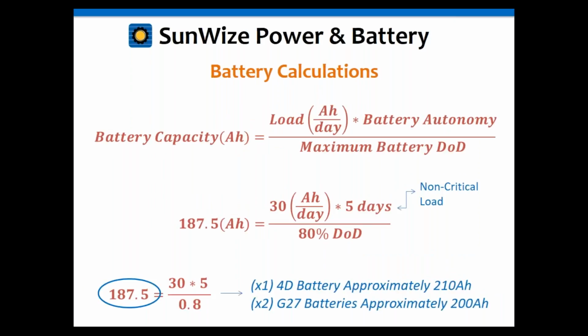Battery calculations are similar. Since we're talking about a non-critical load, we would use 5 days of battery autonomy. If this was critical, we would have used a higher number of about 7 days, and an array to load ratio of about 1.3 to 1.4. Again, I refer you back to the system sizing webinar for that information. So we come up with a required battery capacity of about 187 amp hours. That would be either one 4D battery or a couple of group 27 batteries in parallel.